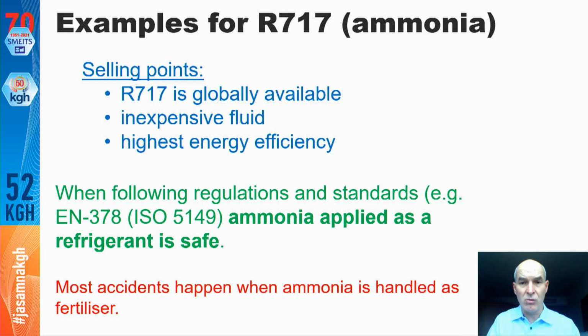So why is ammonia such a good fluid? Because it's globally available, very inexpensive, and has one of the highest energy efficiencies when it comes to these kinds of chiller applications. When you follow the regulation and standards, for example EN 378, ammonia applied as a refrigerant is very safe. Most accidents actually happen when it's handled as a fertilizer.